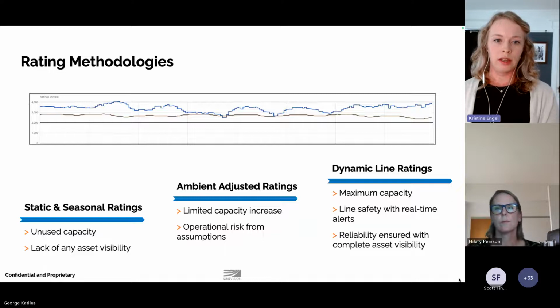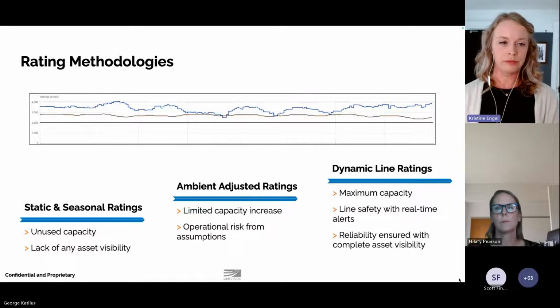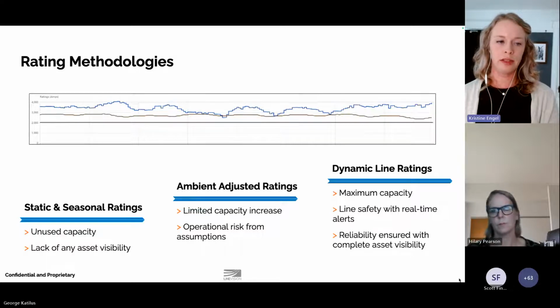Above that, we see a higher line rating with some variation, but not too much. That's the ambient adjusted rating. And up top in blue, we have the dynamic line rating, where we see more variation, but also much more capacity on average.